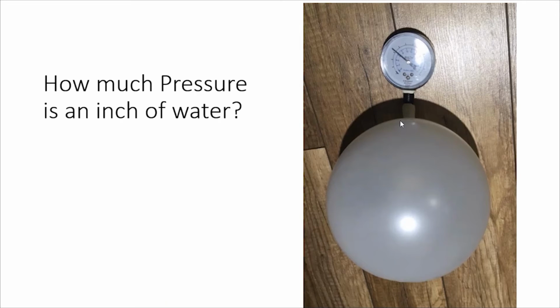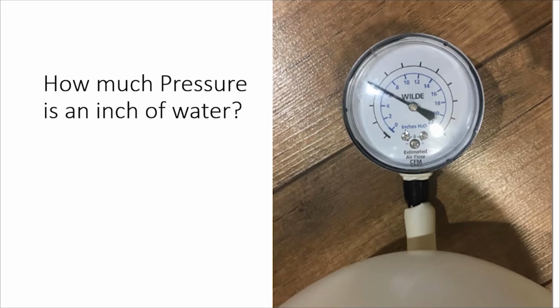Here's just a bit of a feel for how small it is. This is just a normal balloon that I blew up, and I put a static pressure gauge on it, and you can see that reads 6 inches of water. So when we're dealing in inches of water, we're talking about the type of pressure that the human lung can put out, not the type of pressures that an air compressor can put out.